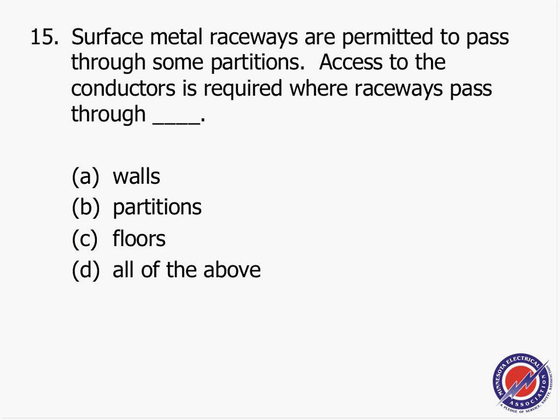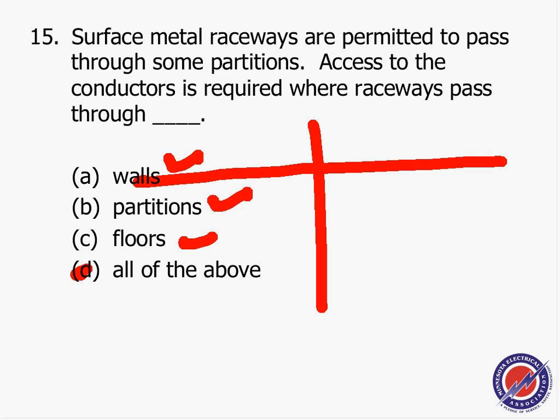Surface metal raceways are permitted to pass through some partition. Access to the conductor is required where raceways pass through. Number 15, D, which is the walls, the partitions, and the floors. We have to have access. Access to the conductor is required where raceways pass through. So you have to have access from both sides of the wall to these conductors.